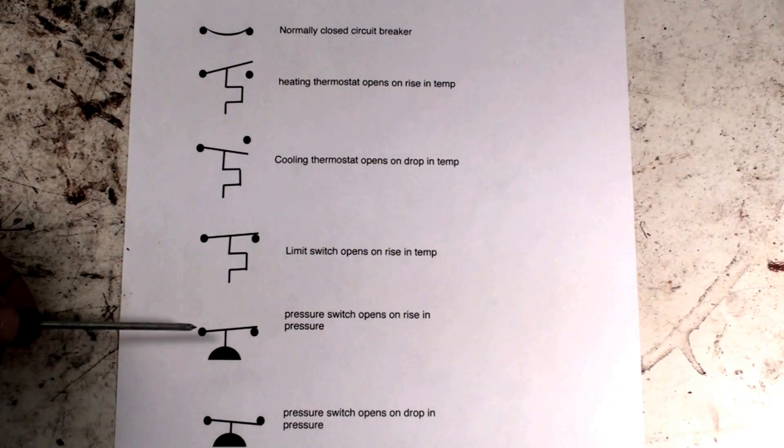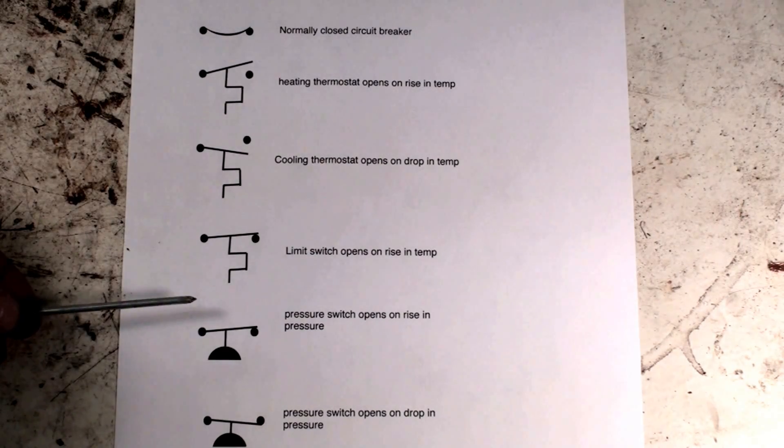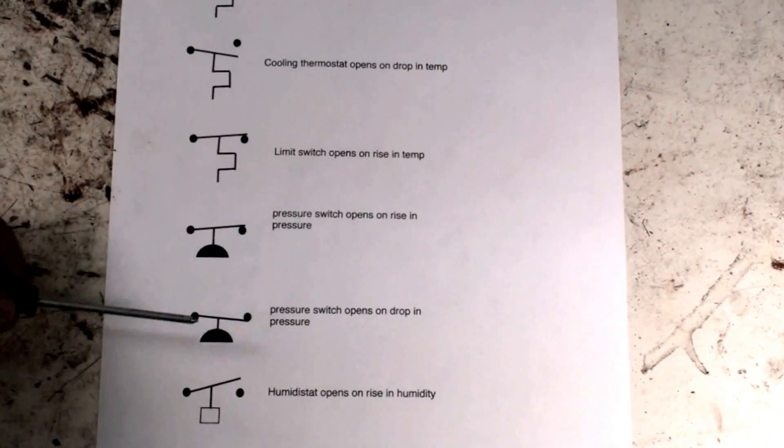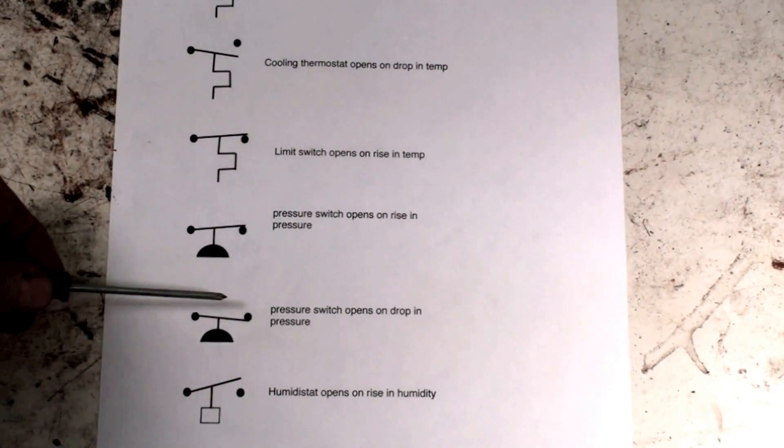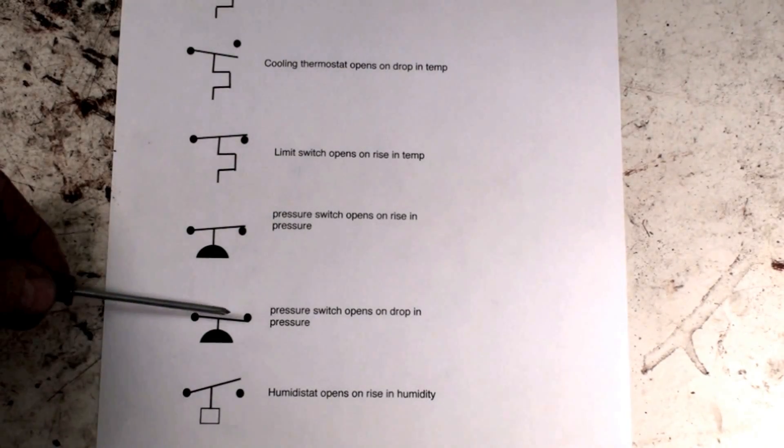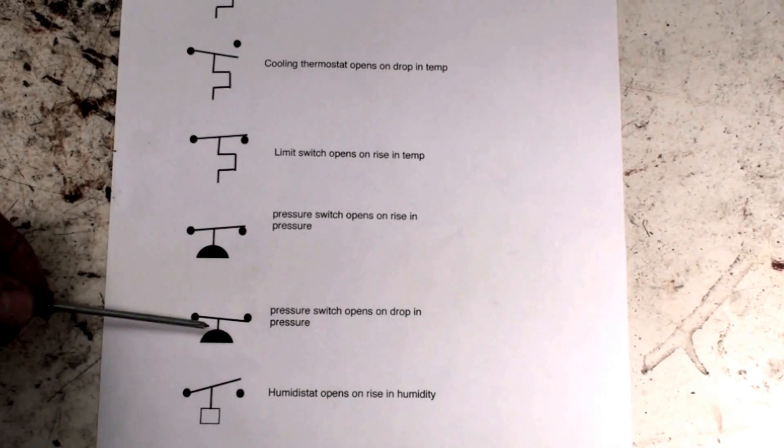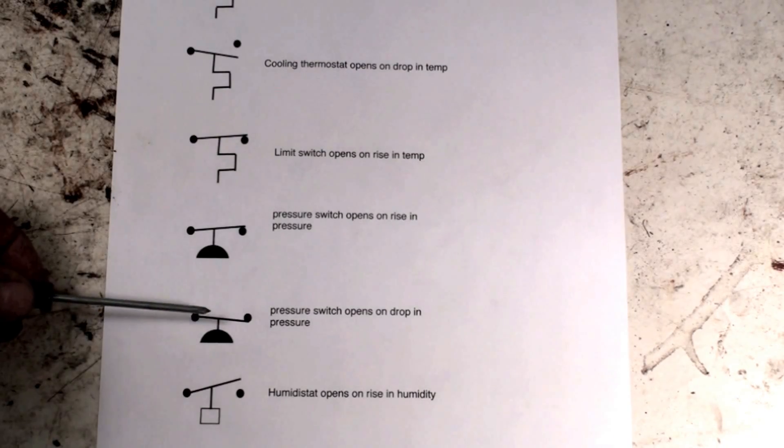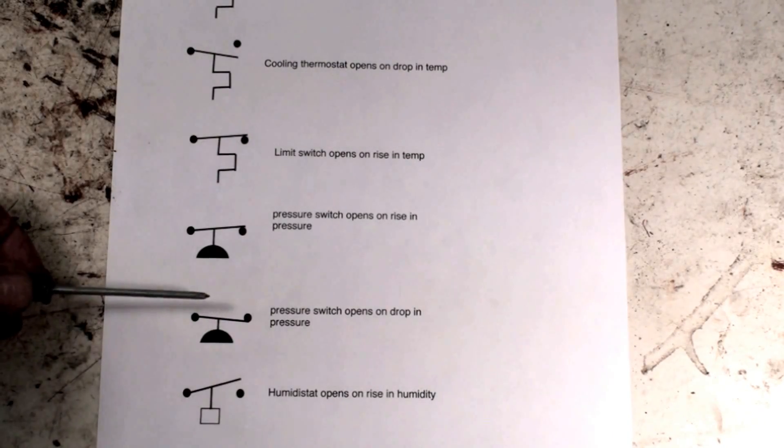This is a pressure switch that opens on a drop in pressure. Again, it's some sort of safety device because it is shown normally closed. If the pressure drops too low, it opens a circuit. Now if this was an operating control, it would be shown open, but these are safeties.